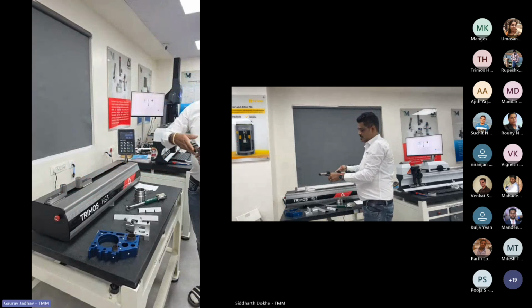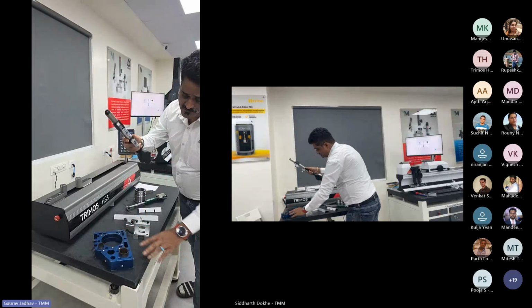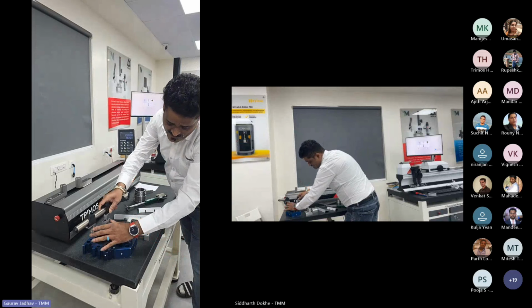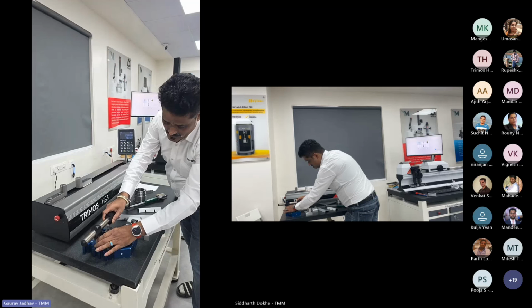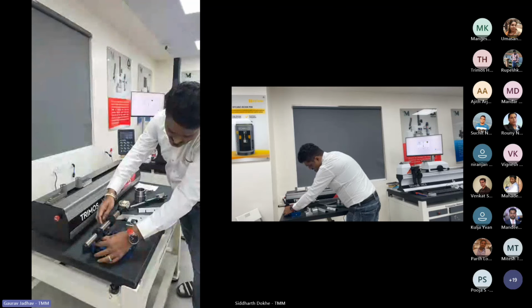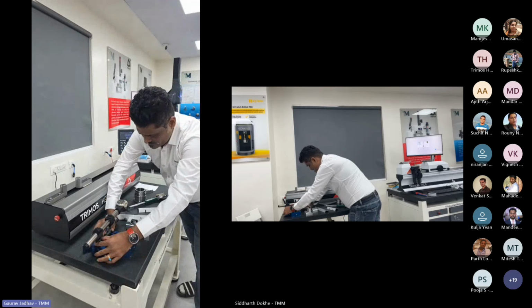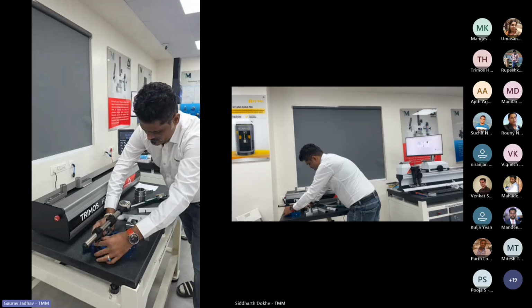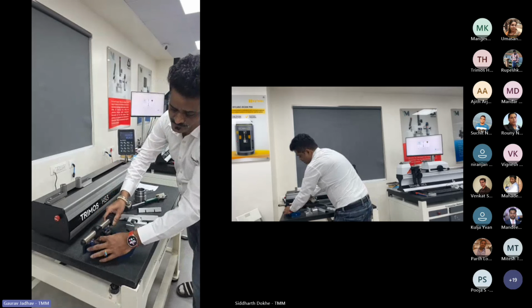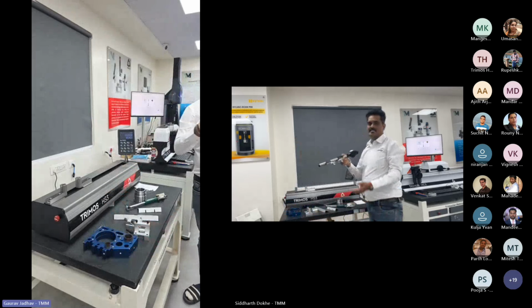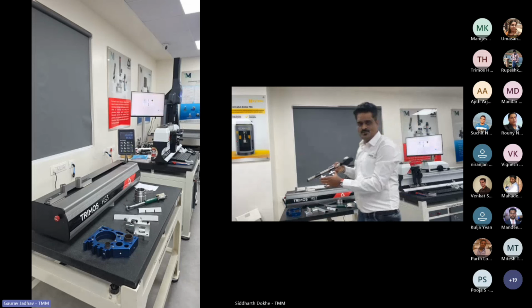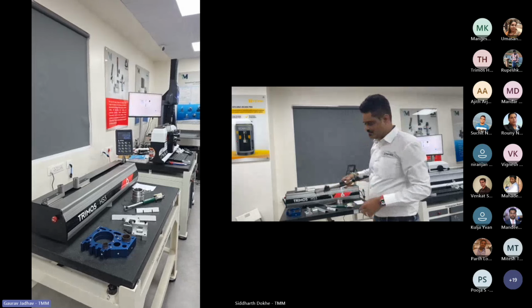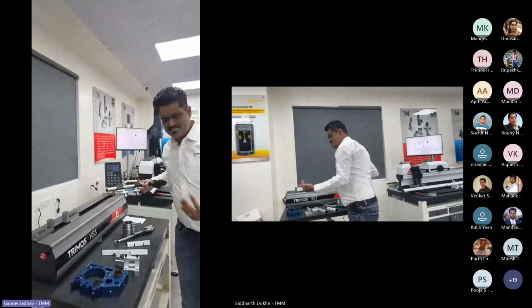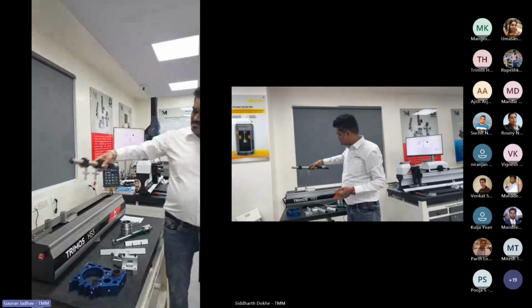You can see. Suppose I want to measure this diameter with the help of the beam gauge. So I'll just enter this beam gauge here, rest on this, and again I will search for the match point. You can see, 95.003 is the size of this bore. So this setup is very easy. You can set beam gauges also very easily on this machine. Just get the accessories and you can straight away set the beam gauge on this.